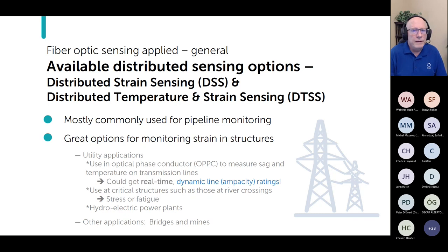Well, heck, on today, October 21st, what's the wind speed outside my house in Texas? Beats me. I don't know. But if it's anything above 1.4 miles per hour or 2.2 kilometers per hour, that would have a significant effect on cooling of the conductor. And so if I had rated a line in my area for 1,000 amps, just to pick an easy number, well, today maybe I could actually get 1,100. And that's important for how I operate my power grid to know if I could get more or not.